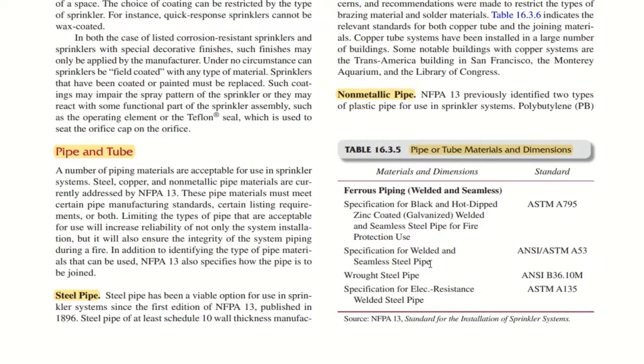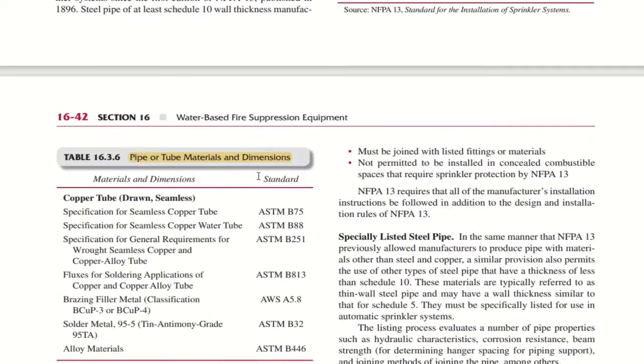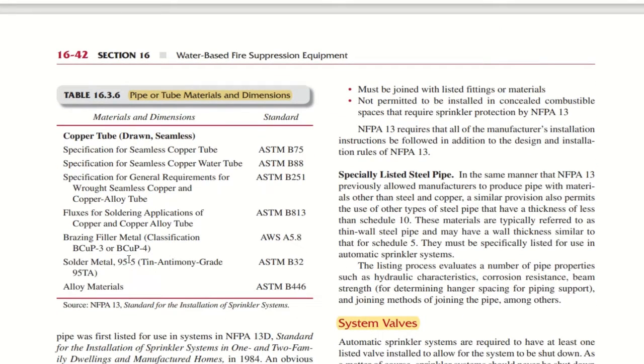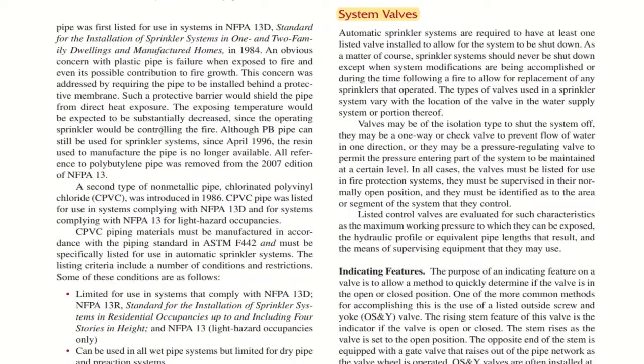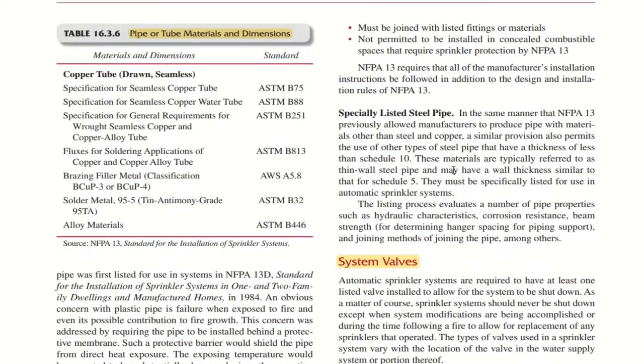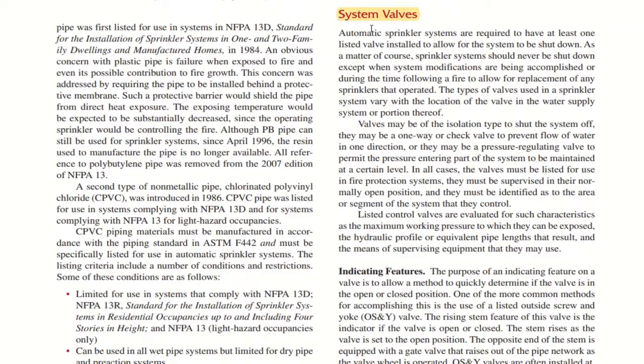If you are using steel pipes, welded type or seamless type, you need to consider ASTM A53 or ANSI standard. So here you have some other specifications for copper tubes. Okay, so this also can be used for our sprinkler system. Piping, you have system valves.